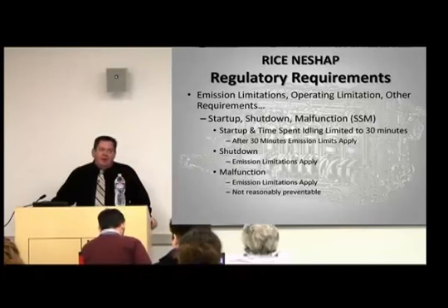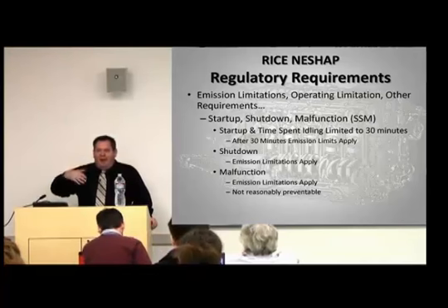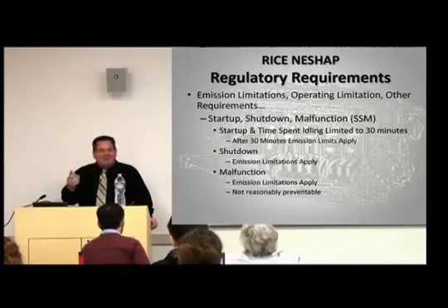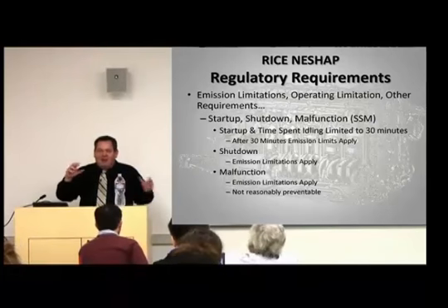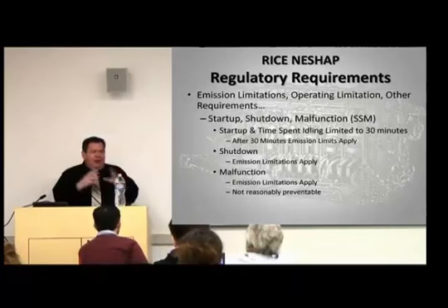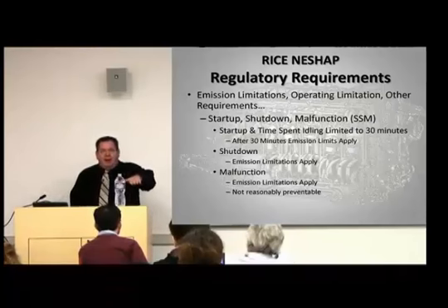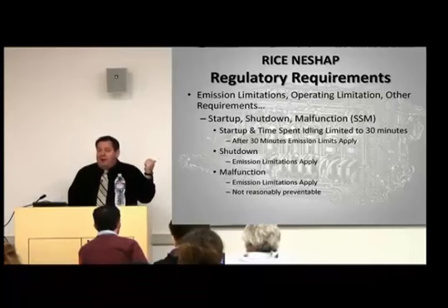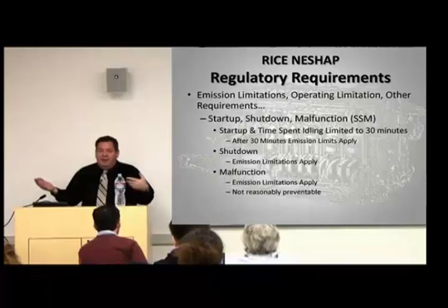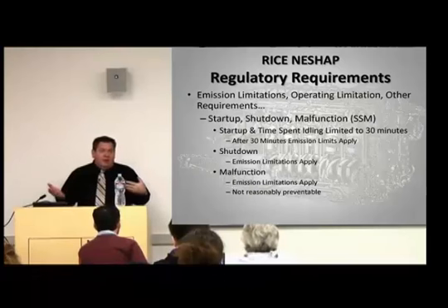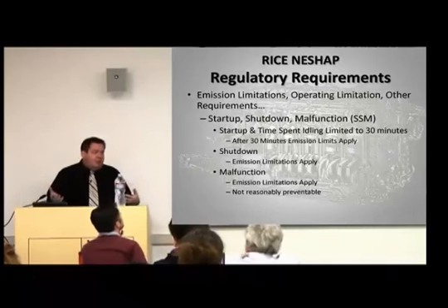No big deal. But you've got some huge behemoth engine that's been running under a heavy load for hours, days, weeks, months. You don't just pull the load off and turn off the engine, because some parts of the engine are really hot and some parts are substantially cooler, and the temperature difference can have catastrophic effects. So you have to remove the load and bring the engine slowly back down to idle. The emission limits apply. They can't do it willy-nilly. They have to do it either while they're monitoring with a CEMS or CPMS, or they have to have some plan to do it.